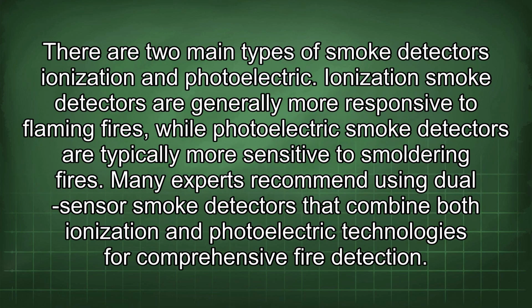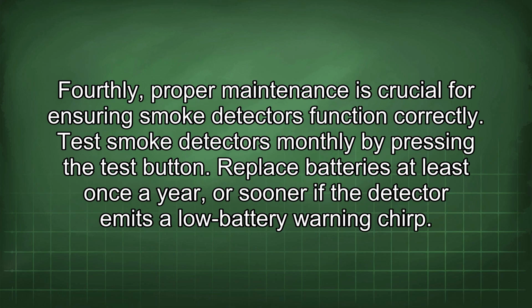There are two main types of smoke detectors: ionization and photoelectric. Ionization smoke detectors are generally more responsive to flaming fires, while photoelectric smoke detectors are typically more sensitive to smoldering fires. Many experts recommend using dual-sensor smoke detectors that combine both ionization and photoelectric technologies for comprehensive fire detection. Fourthly, proper maintenance is crucial for ensuring smoke detectors function correctly.